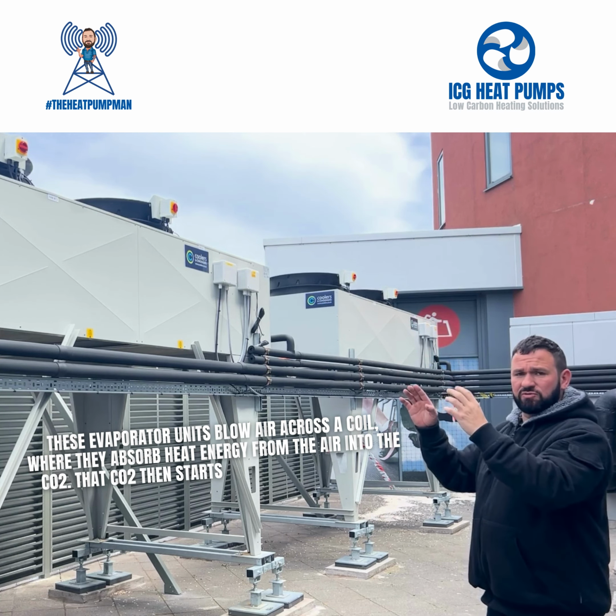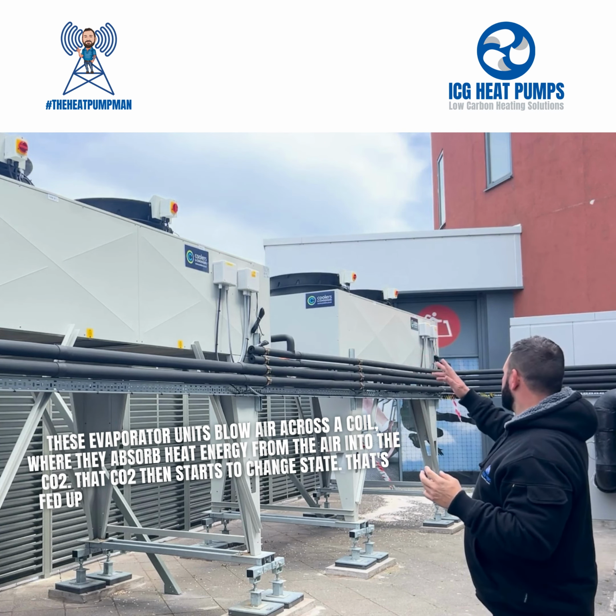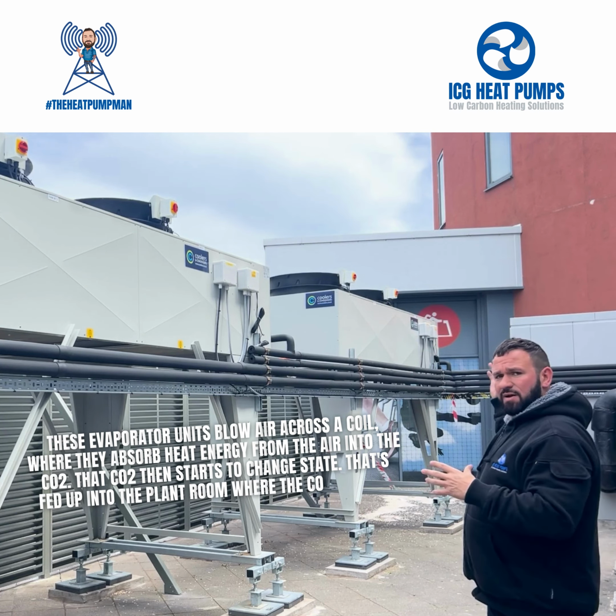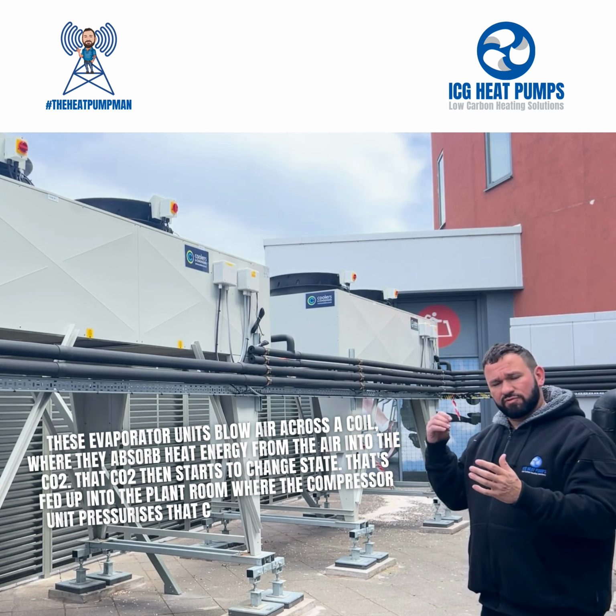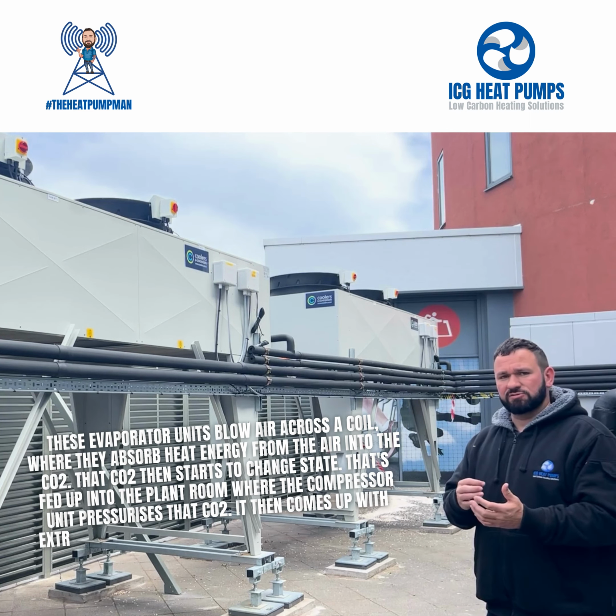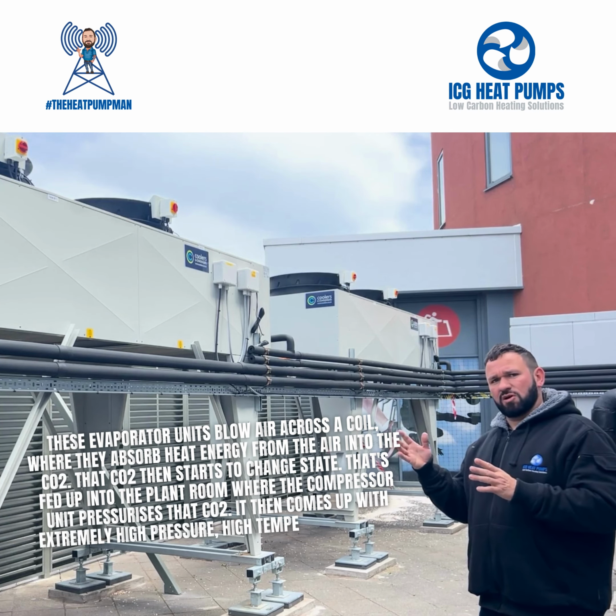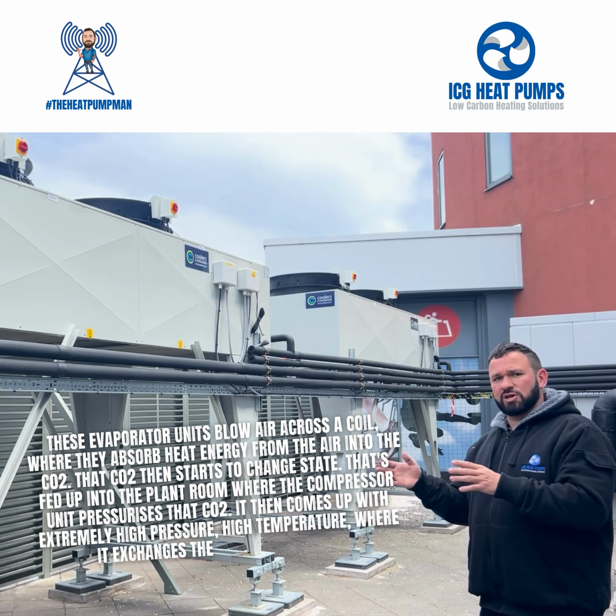into the CO2. That CO2 then starts to change state. That's fed up into the plant room where the compressor unit pressurizes that CO2, then comes off extremely high pressure, high temperature, where we exchange the heat to the water.